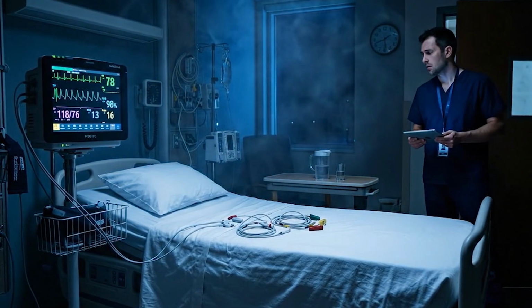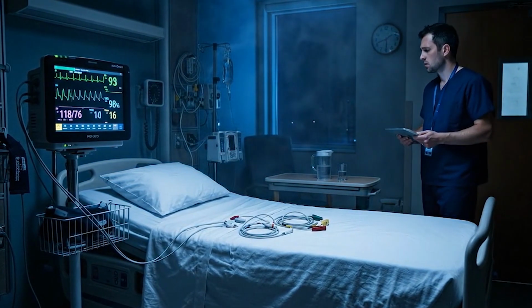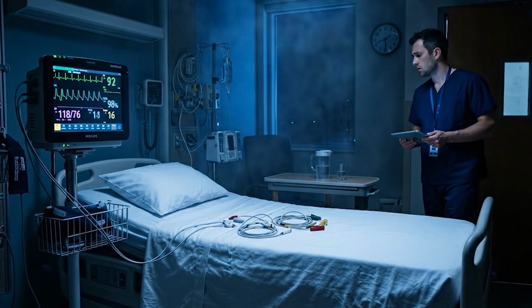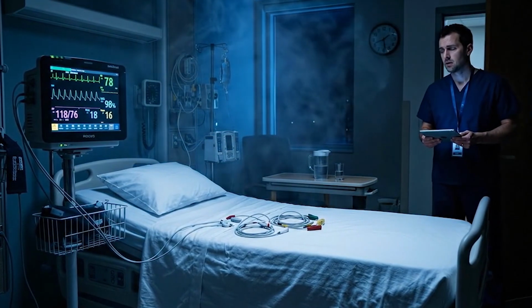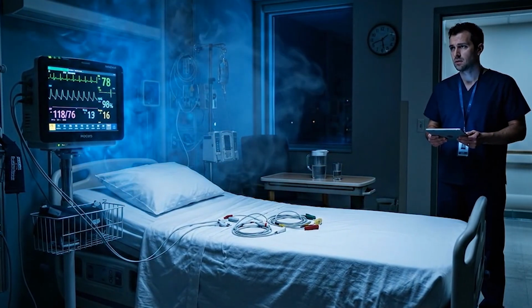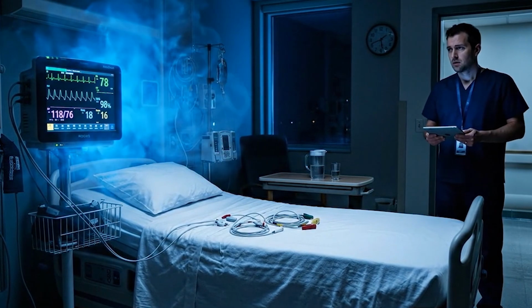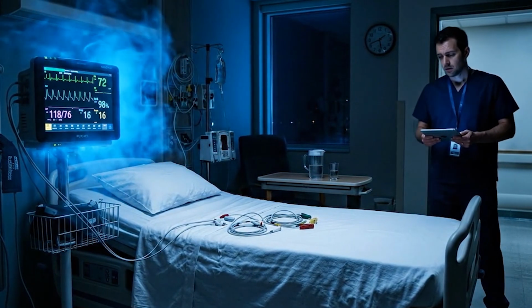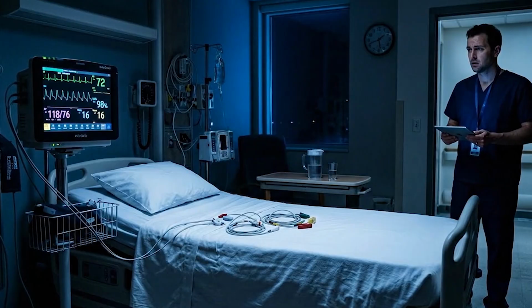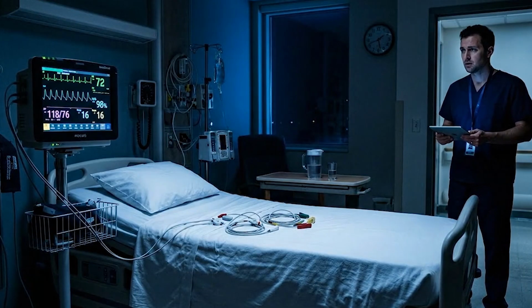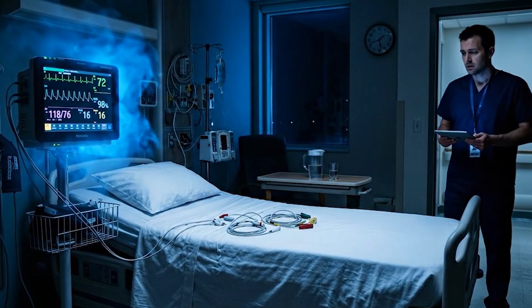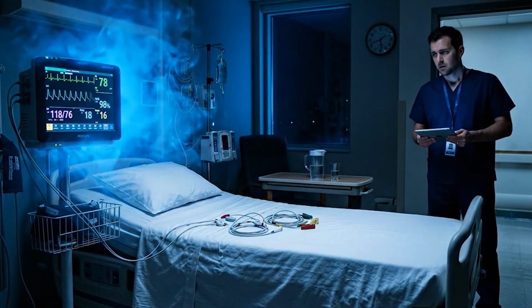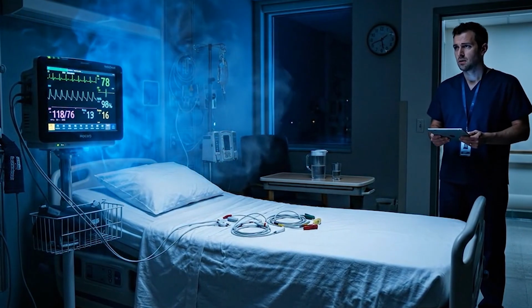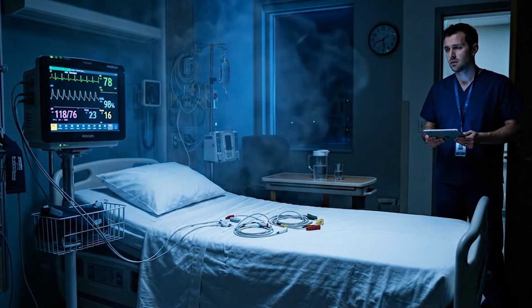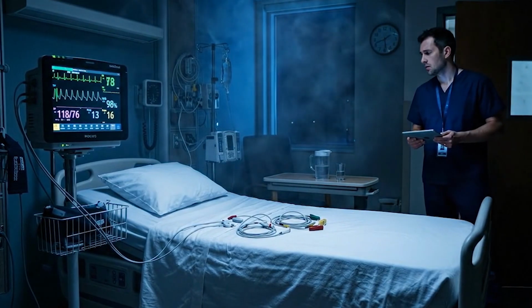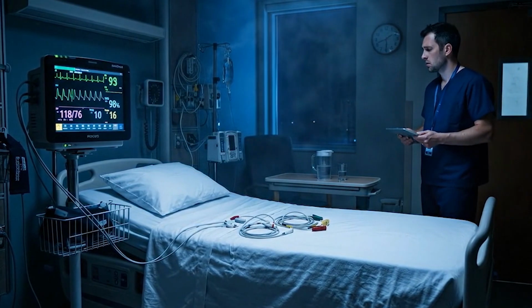They're the industry standard for acute cardiac care. I've serviced hundreds of them. They don't generate phantom data. When a monitor isn't connected to a patient, when the leads are disconnected, the cuff is off, the pulse ox probe is hanging, it shows flat lines or a leads off error message. It does not show a heart rate of 72. It does not show blood pressure. It does not invent a patient.